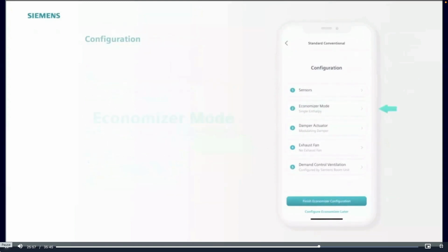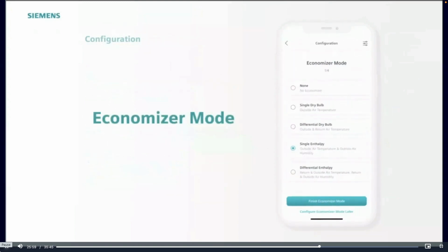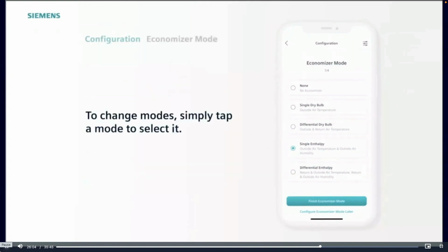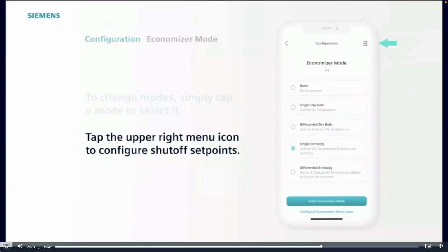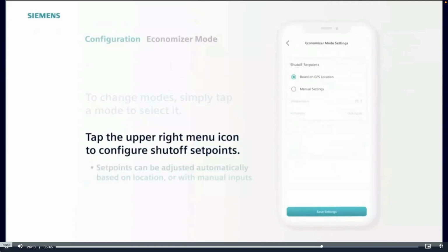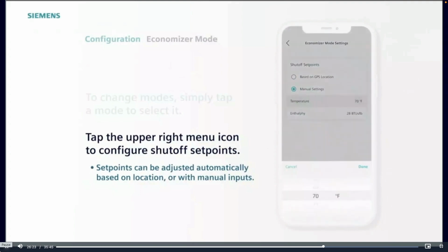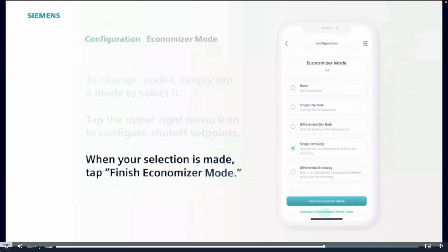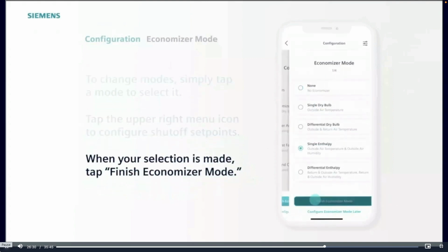Next is economizer mode. Tap to open. Single enthalpy is a preset here to match the sensors provided in our RTU kit. To use a different economizer mode, simply tap to select it. You can configure your shutoff set points based on GPS location or manual settings. If you do it based on GPS location, the application will look up a climate zone that you are in and automatically download those parameters. Otherwise, you can manually adjust the temperature setting. For this example, we'll set it to 68 degrees. When you're happy with your selection, tap Finish Economizer mode.